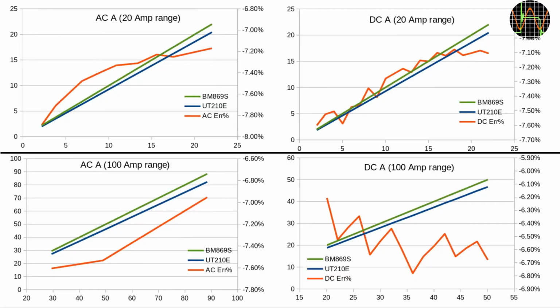Here are the results before calibration. You can see that the error of around 7% for the 20 amp and 100 amp range is pretty much similar to the one I had in the 2 amps before I did the calibration. In all cases, we have the blue trace diverging more and more from the green one when the current gets higher, and a simple recalibration with a new correction factor can fix this. While I was doing the patching of the 60 amp and 600 amp cal values in the EEPROM, I decided to try changing the count from 2000 to 6000 as well.